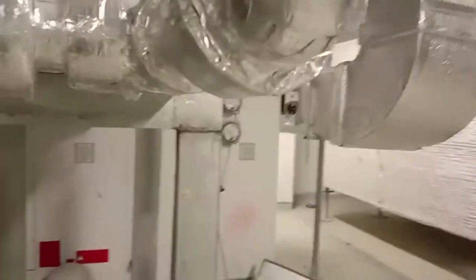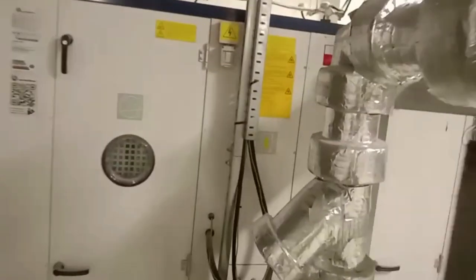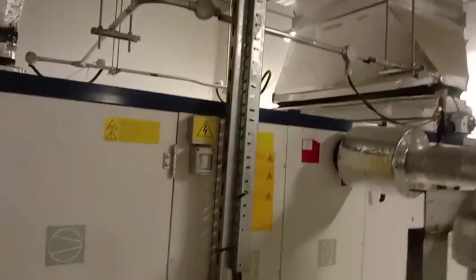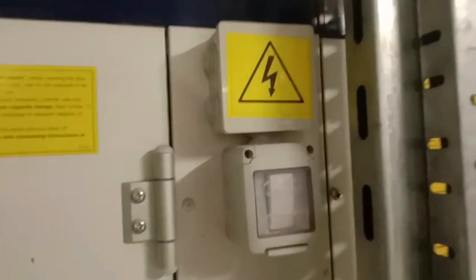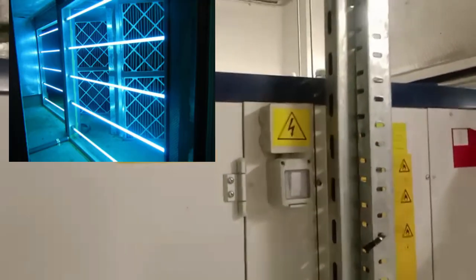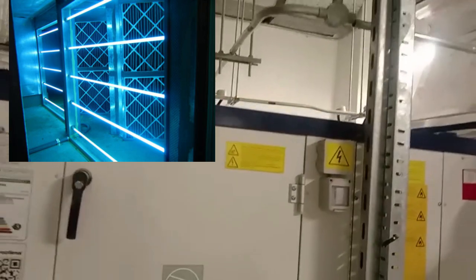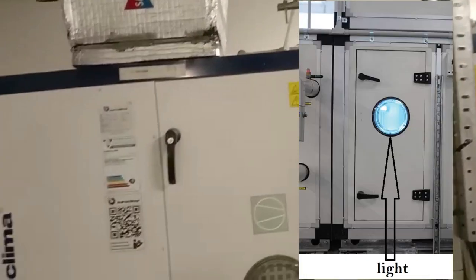I'll take us now to the electrical side. We've carried out the cable tray, which is done. Cable pulling also done, grounding and termination done as well, which is connected to the motor. So we have this light switch, which is used to control the light inside the AHU. During maintenance, we'll be able to see inside, and then we carry out our maintenance.